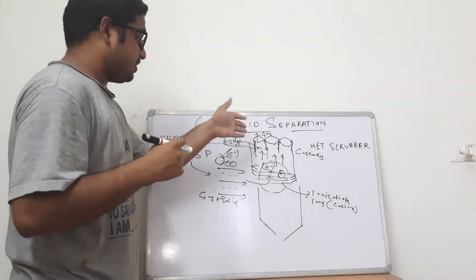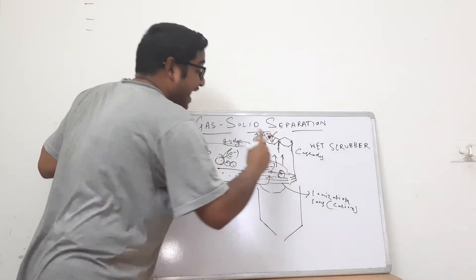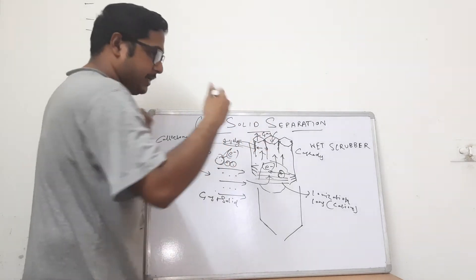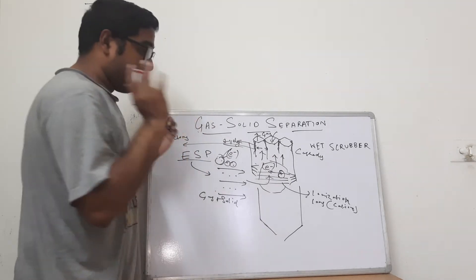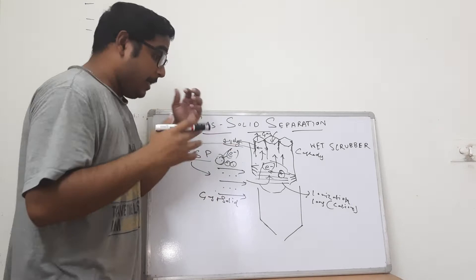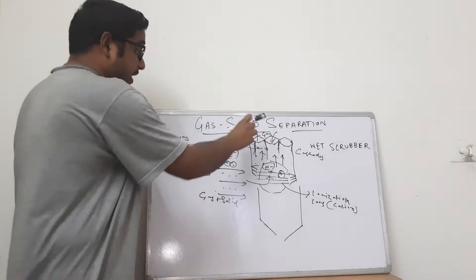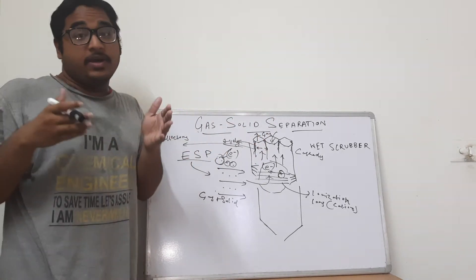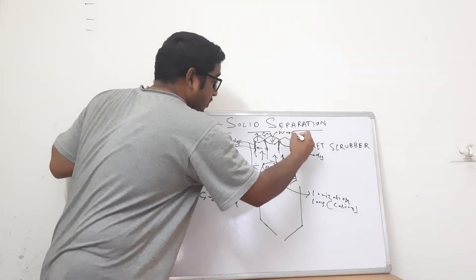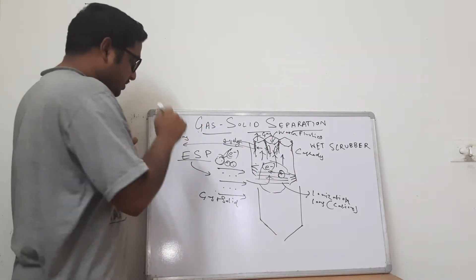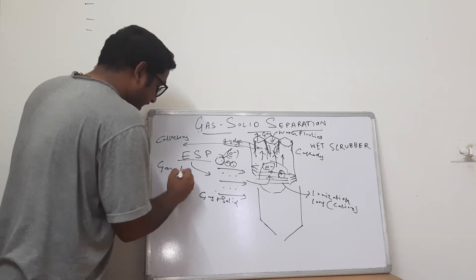The system needs to be flushed multiple times a day. Flushing means — similar to the reverse jet of air used in bag filters to scrape off dust particles — in ESPs you need to purge whatever is collected on the electrodes, otherwise fresh solid particles cannot deposit because there is already a layer of solids on the electrode surface. Instead, we pass water flushing or air flushing, which creates pressure such that the solid particles get washed out.